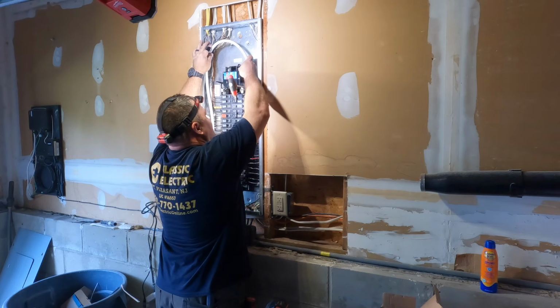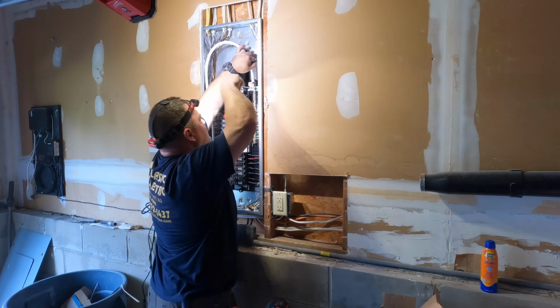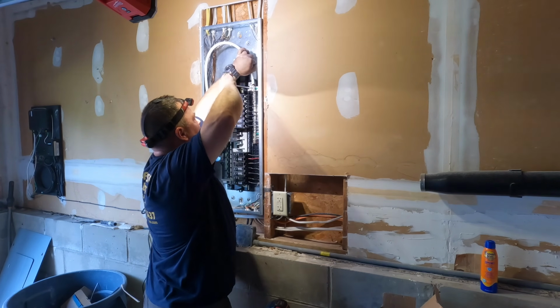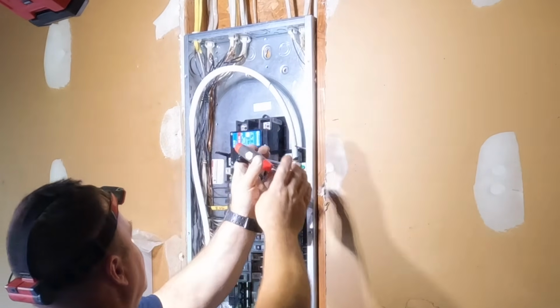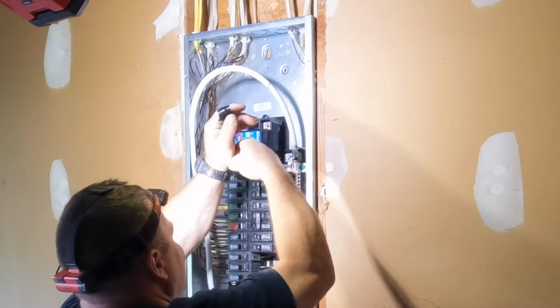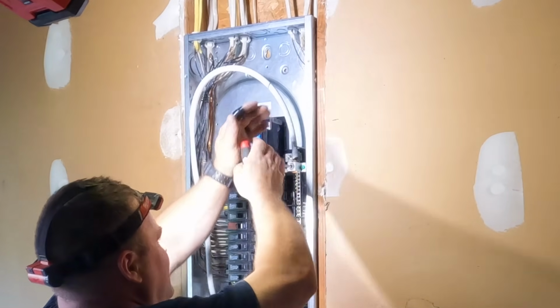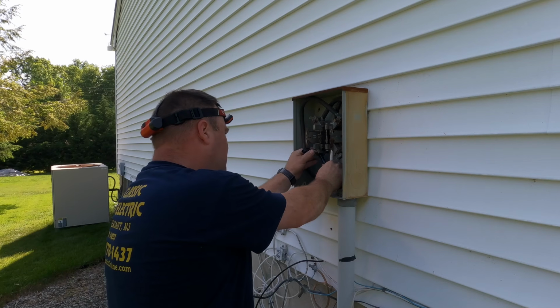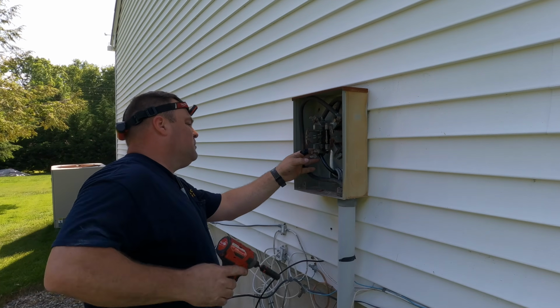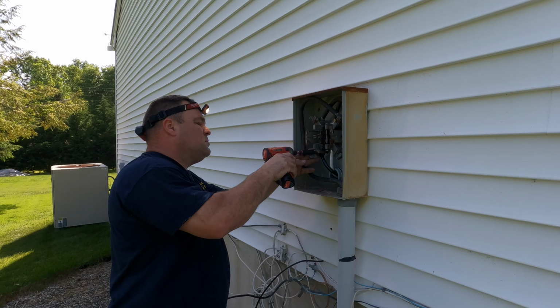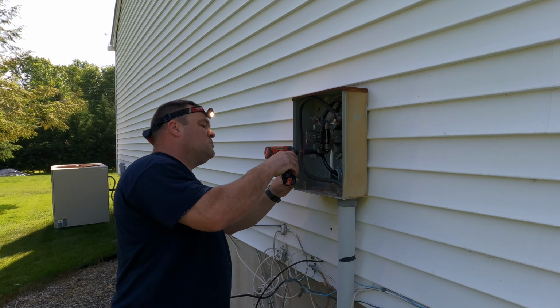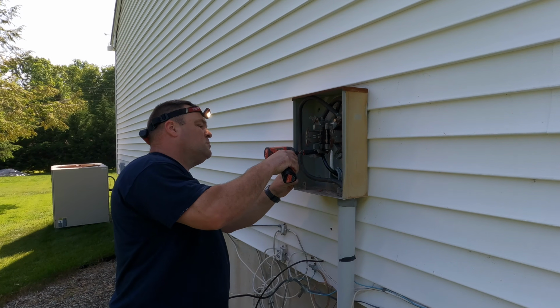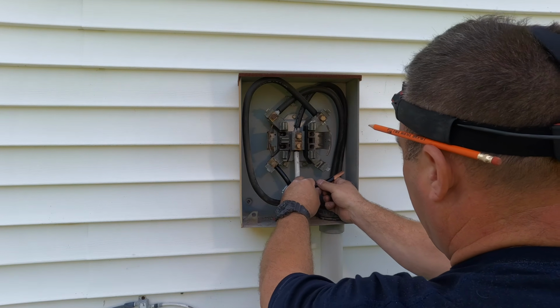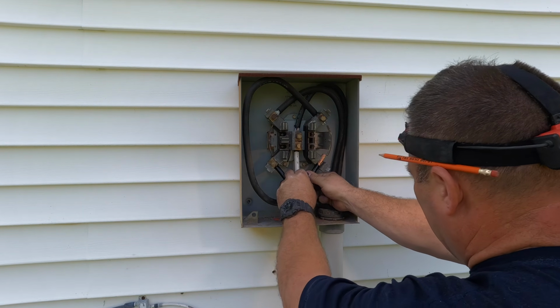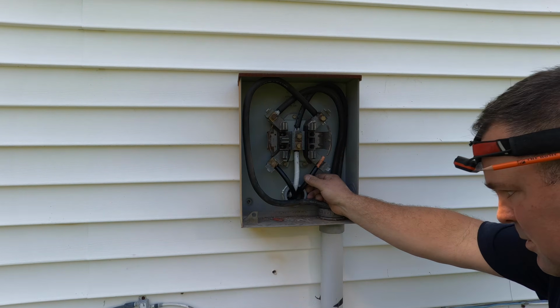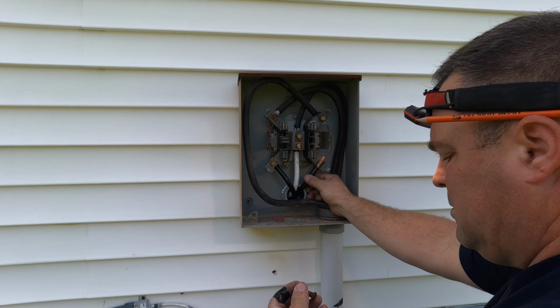And then back on the inside, where I've got plenty of slack and conductor space to terminate, obviously you want to do this second. You want to do the hard one first and then the easy one second. And then I'll just do 2 more conductors on either side of the load side of this meter. I'll attach them on the outside and then on the inside again until I have all 3 service entrance conductors: 2 hots, and that grounded neutral is the white wire.